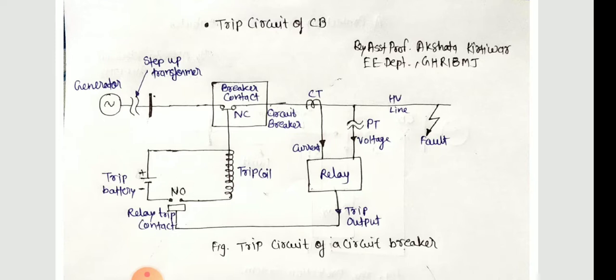When the trip coil is energized, it releases a latch, causing the stored energy in the opening spring to bring about a quick opening operation.